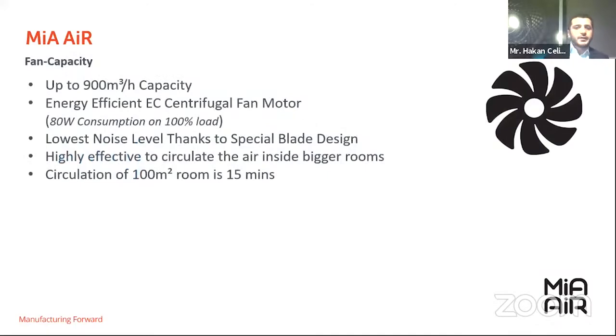If we discuss the airflow rate, we have used a very strong fan on this machine. Actually, there are lots of stronger fans in the market, but from the point of engineering, we have mostly focused on the highest airflow, lowest energy consumption, lowest noise level, and longer lifetime. Focusing on these factors, we have used a special fan which has a capacity of 900 cubic meters per hour, and it's an electronically controlled fan for variable speed use. It's able to recirculate the air inside a 100 square meter room in only 15 minutes. So in a room of 100 square meter area, you can circulate the air 4 times in 1 hour.